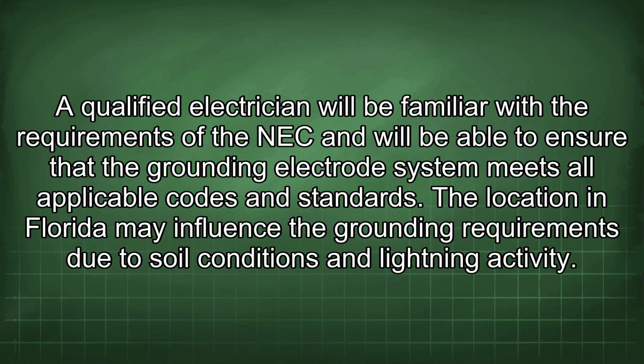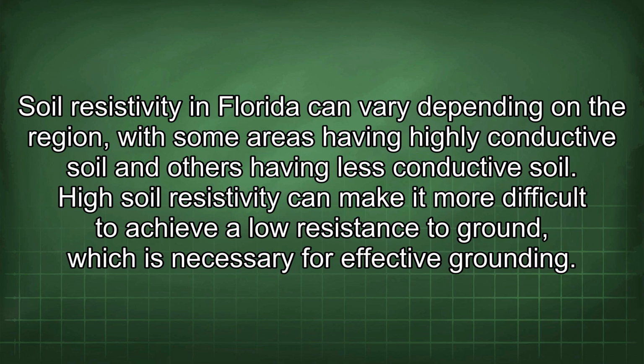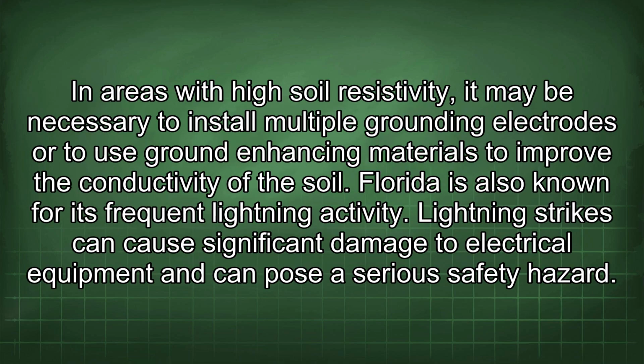The location in Florida may influence the grounding requirements due to soil conditions and lightning activity. Soil resistivity in Florida can vary depending on the region, with some areas having highly conductive soil and others having less conductive soil. High soil resistivity can make it more difficult to achieve a low resistance to ground, which is necessary for effective grounding. In areas with high soil resistivity, it may be necessary to install multiple grounding electrodes or to use ground-enhancing materials to improve the conductivity of the soil.